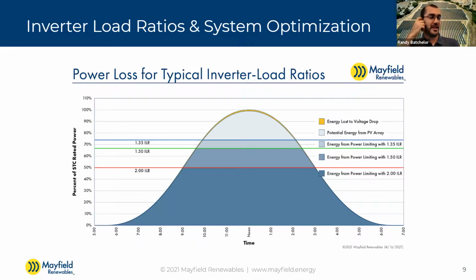There's a new code section, in 2020, where you can actually limit the current input on your inverters. If you've got a combiner box, you can limit the size of your DC conductors to the inverter input limit. So whatever the inverter is capping the DC input at, rather than sizing those conductors for the output of your solar, you know it's never going to exceed the rated input of the inverter, so you can size your conductors down.